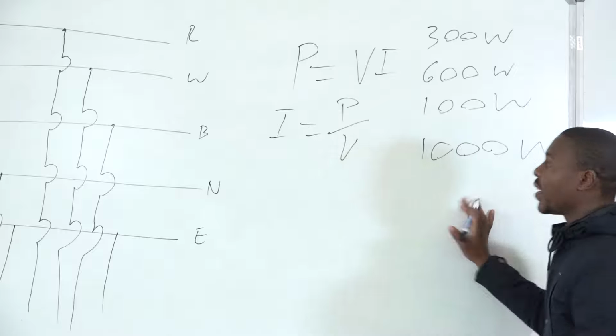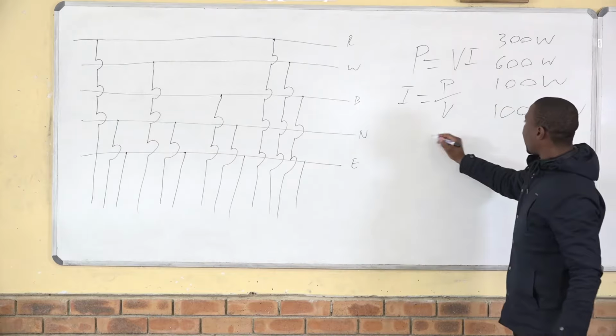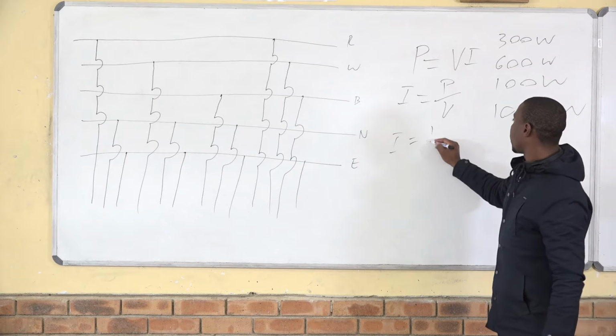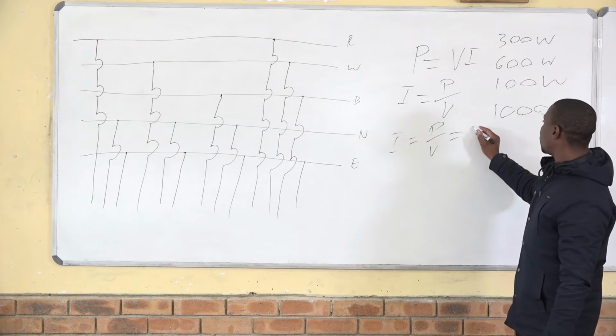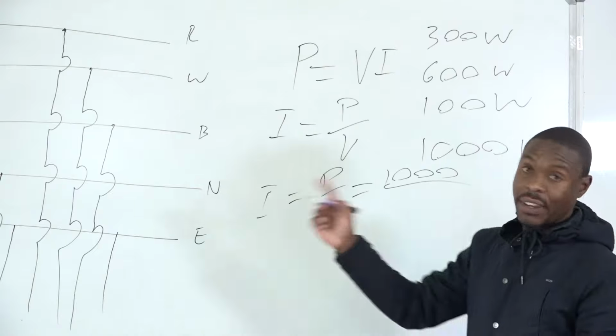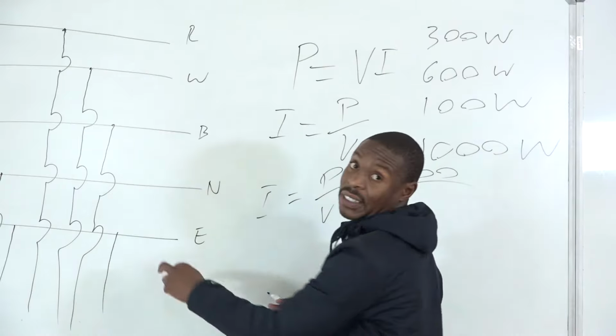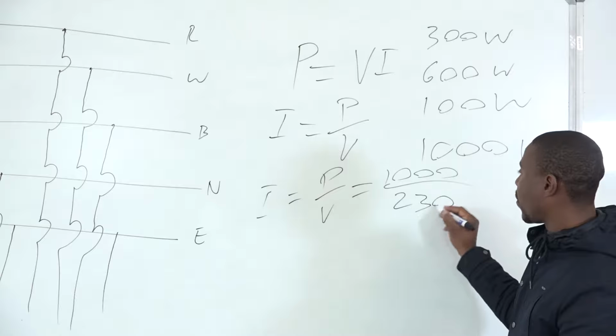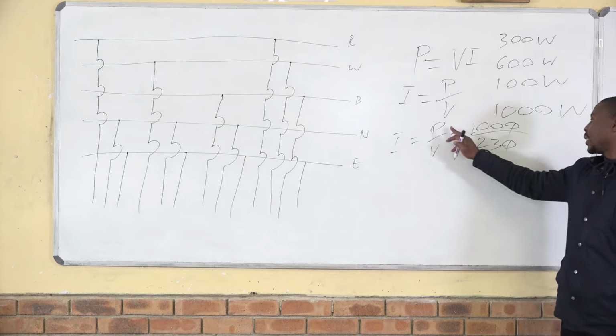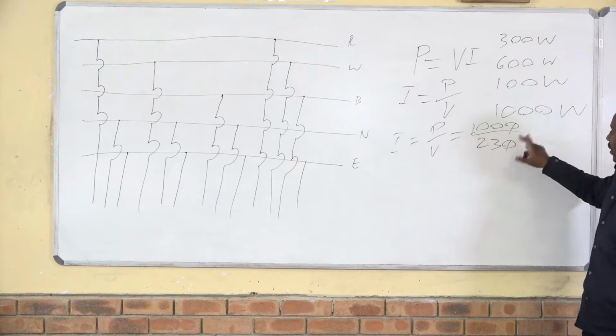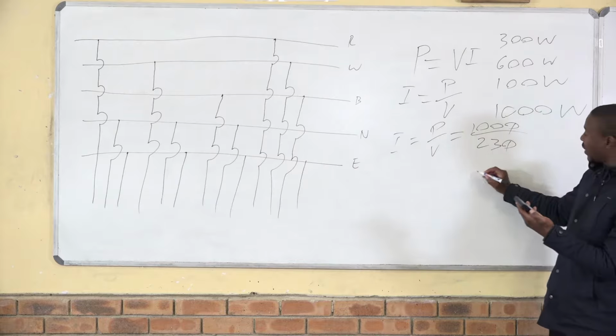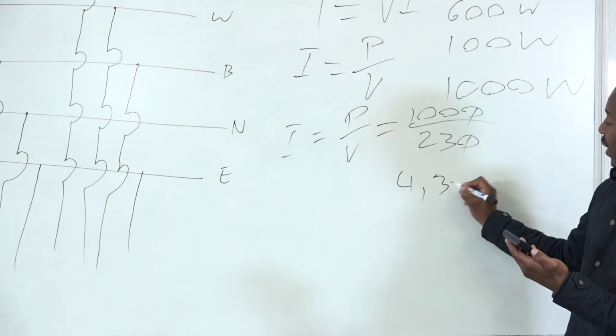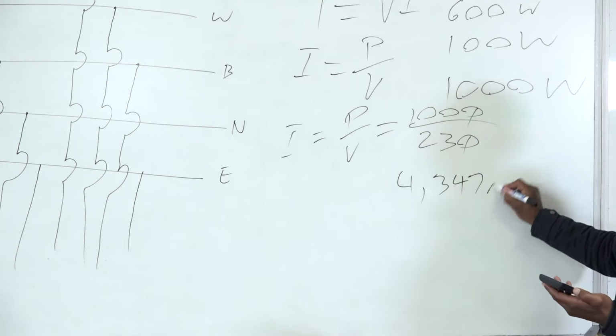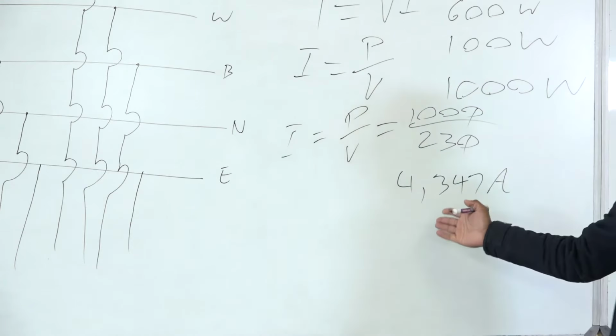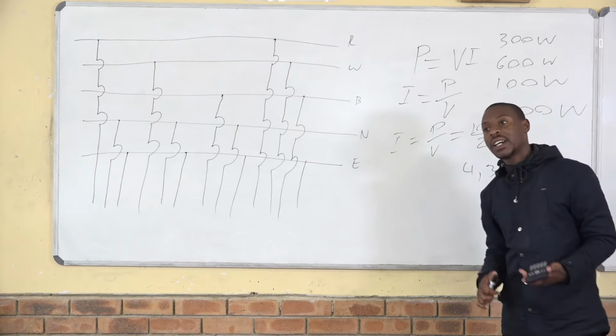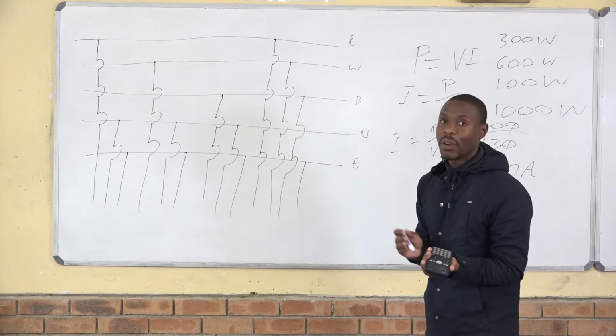This is just an example. Then you manipulate the formula. You say I is equal to P over V. And then you put your 1,000 watts, you divide by the given voltage, which, being single phase, will be 230 volts. I is equal to P over V. This is power, this is your voltage. Then you divide 1,000 by 230. Then you will get 4.347 amperes. Then now you see that this amperage doesn't exceed the 63 amp that you are given as a consumer. So that's why we balance a load.